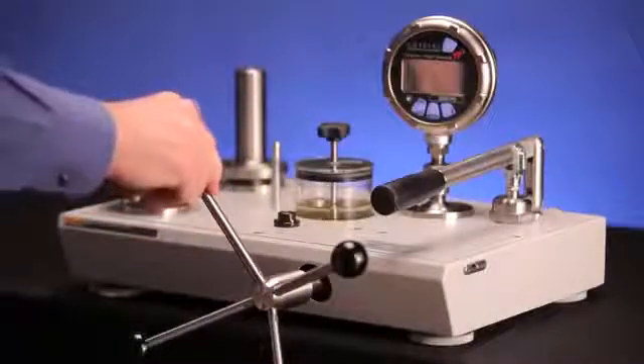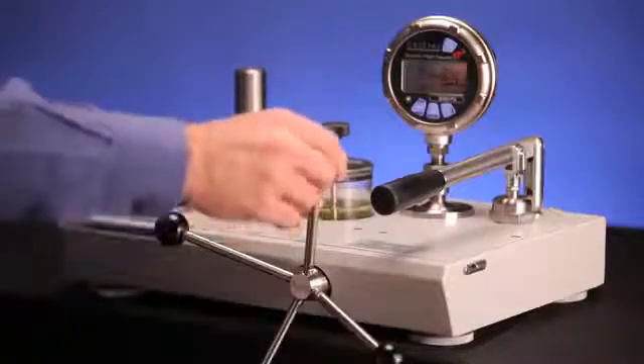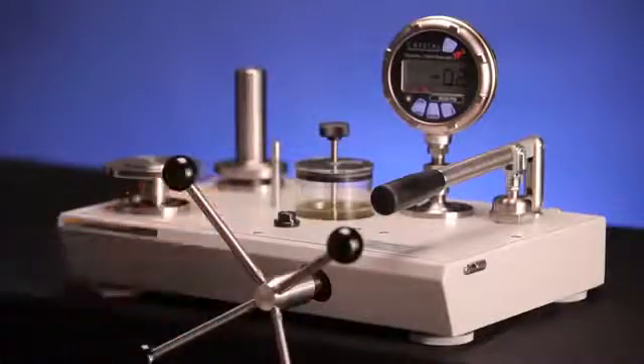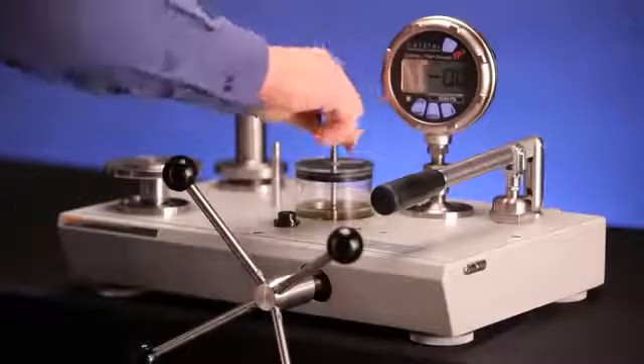Once the variable volume is fully out, open the reservoir valve and turn the variable volume fully in. To finish the process, turn the variable volume fully out with the reservoir valve open. Once it is fully out, close the valve. The tester is now ready for use.